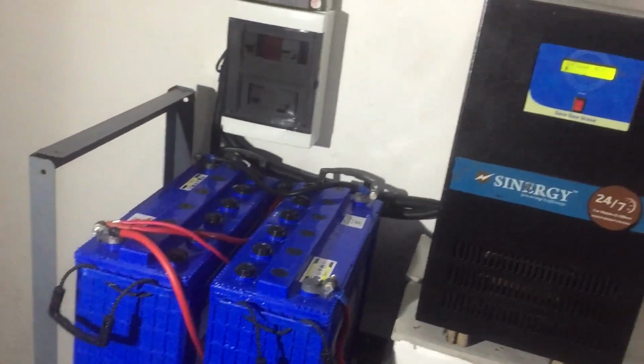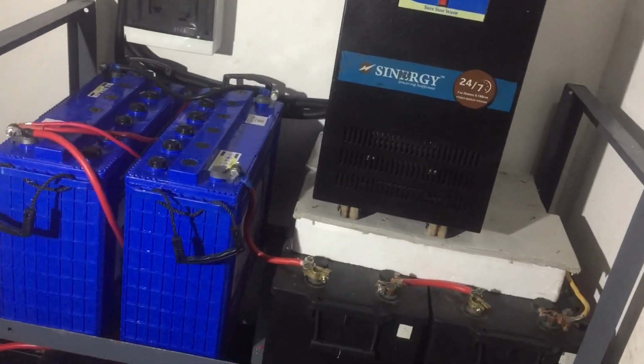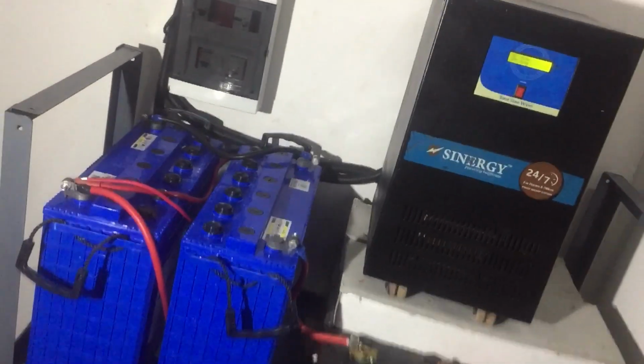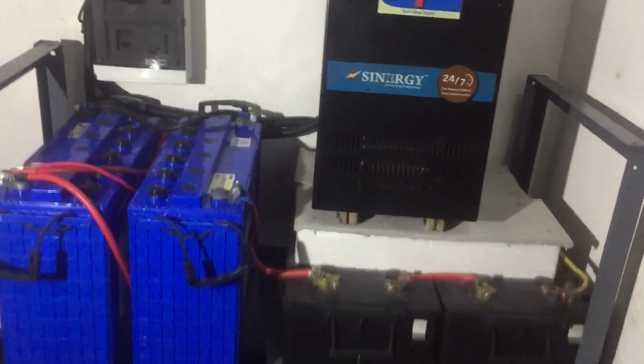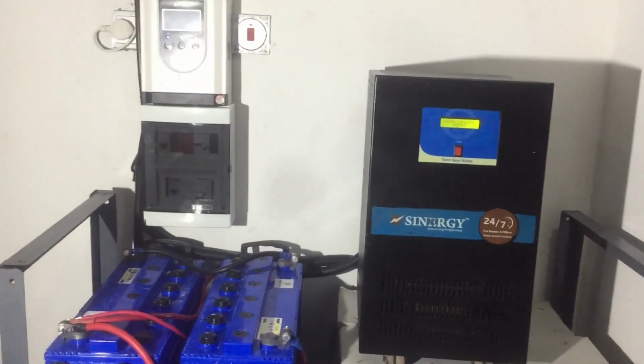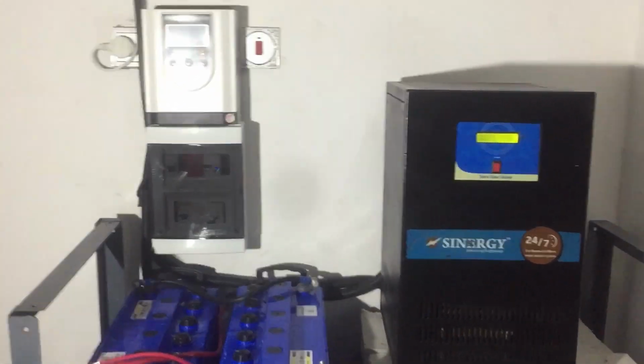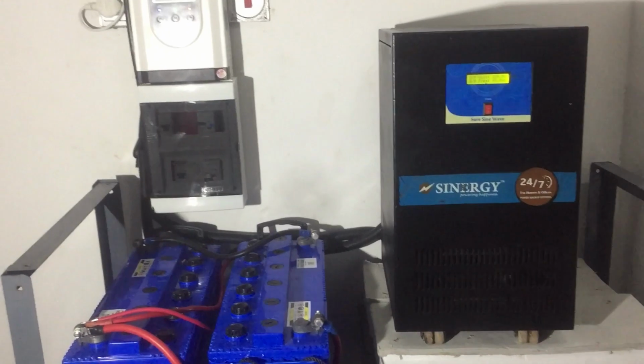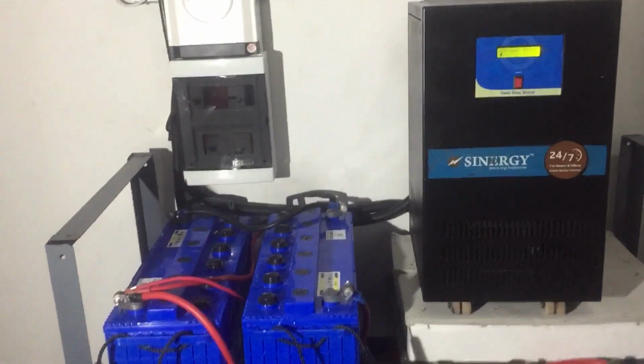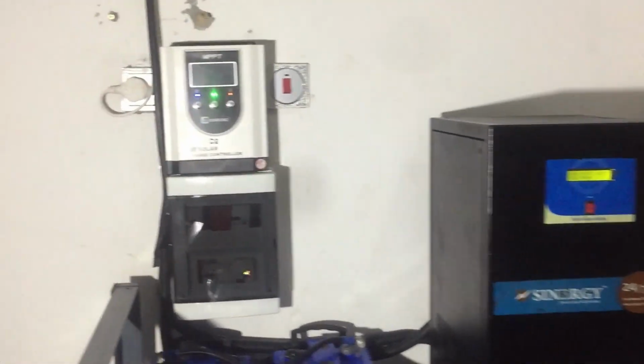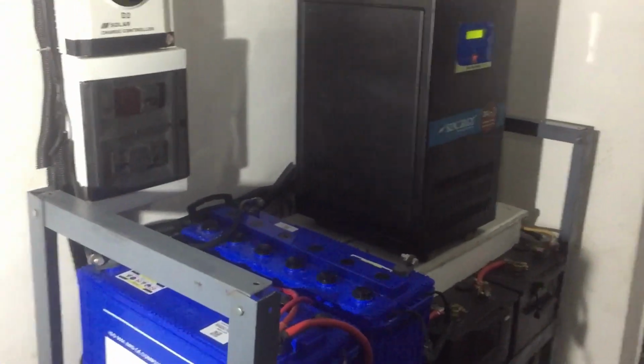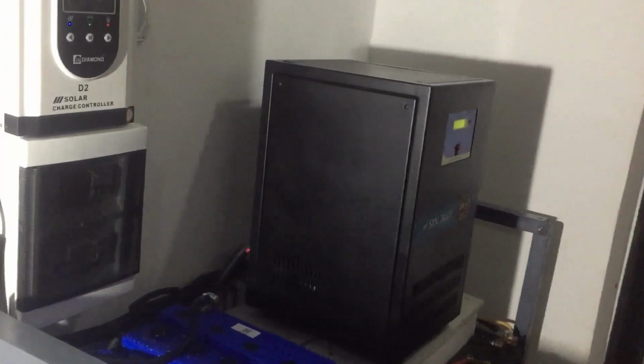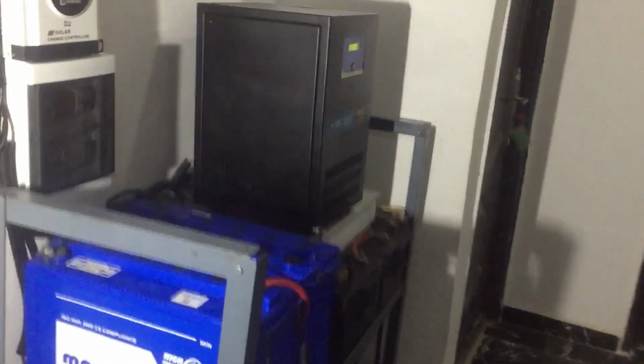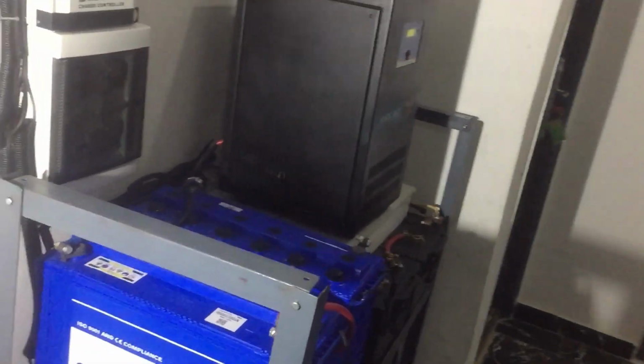So it may have a problem, possibly, if it is other types of flooded batteries. Because if you must add the batteries together, you have to make sure that it is the same type of battery. If it is the same type of battery, it will help the inverter to be able to charge the batteries effectively. Because in a situation where you have a sealed battery mixed with a tubular battery, there will not be effectiveness. It will not work very well.